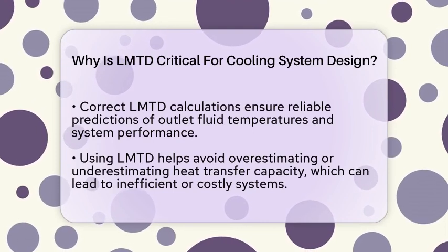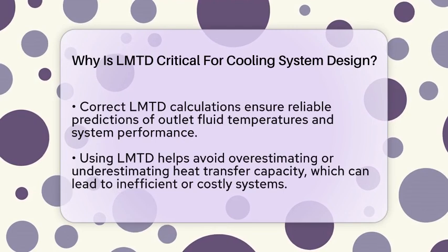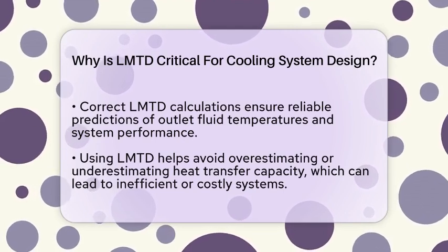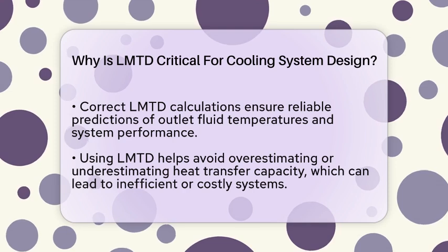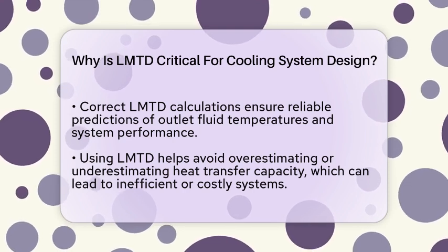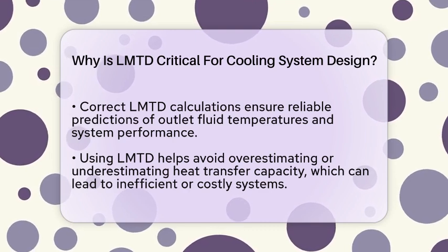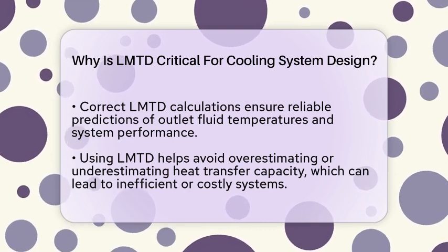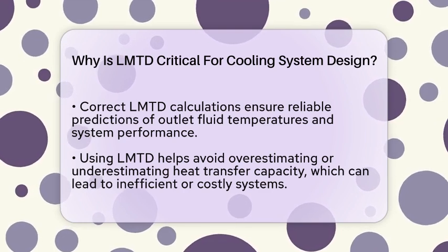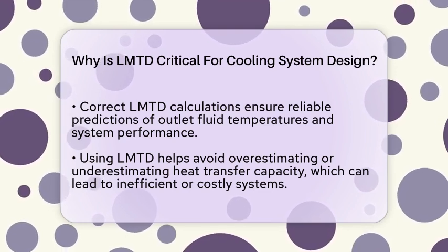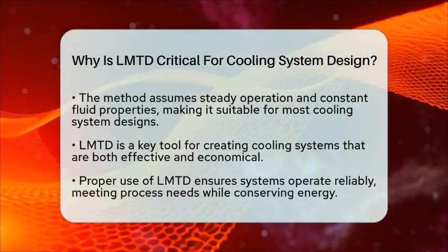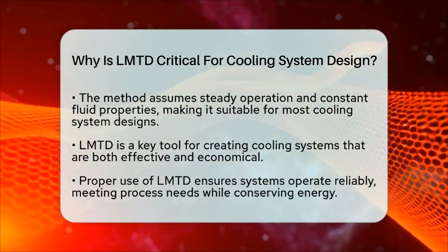It also helps in sizing the heat exchanger correctly, ensuring it can handle the required heat load without wasting resources. When the LMTD is calculated correctly, it makes predicting the outlet temperatures of the fluids more reliable. This helps ensure the cooling system meets the process needs and operates efficiently. Without LMTD, engineers might overestimate or underestimate the heat transfer capacity, leading to systems that do not perform well or cost too much to run.